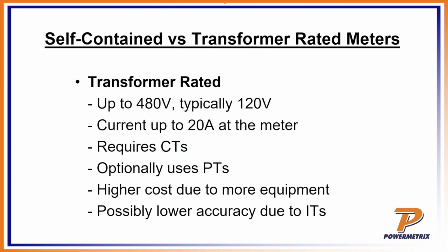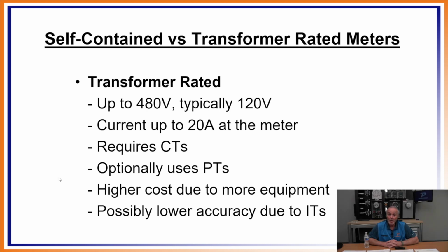You can also use PTs to bring the voltage down. You can bring the current down, and you can also bring the voltage down. Right up in that first line, it says 480 volt, but typically 120 volt. So a 4-to-1 PT would take 480 volts and give you a fourth of it on the secondary side, so you'd have 120 volts, which we like working with a lot better than 480. But it is higher cost due to more equipment, because you're having to add the CTs and the PTs and other components. And plus, as you add these components, they each have an accuracy level themselves, right?